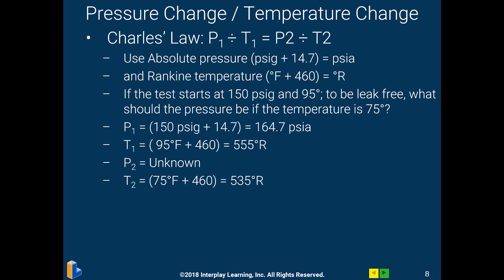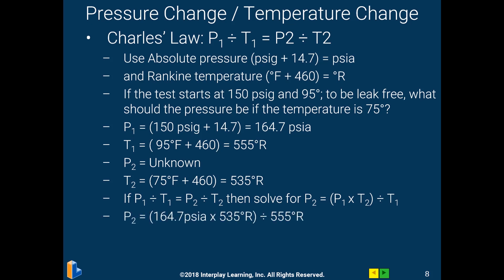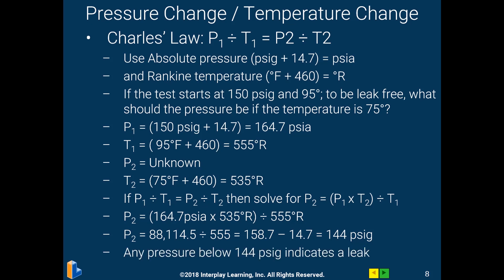We do know the temperature is 75 degrees in the morning, or converted to 535 degrees Rankine, and then we solve for P2, which is the pressure the next morning. Once you do the math, it comes out to 144 PSIG. This means we didn't lose an ounce of nitrogen in the system — the only reason the pressure went down was because the temperature went down. Any pressure below 144 PSIG would mean there's a leak.